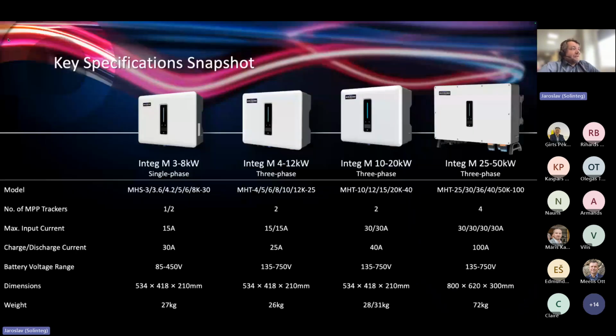Here again are snapshots of our hybrid inverters, from single phase to three phases, already described. Claire will tell you more about the 50 kilowatt inverter. Maybe one important thing for the inverters 10 to 20 kilowatts and 25 to 50 kilowatts: this inverter has a maximum input current for MPPT of 30 amps, so you can connect really any kind of solar modules. All the other inverters have 15 amps per input. This is still enough.